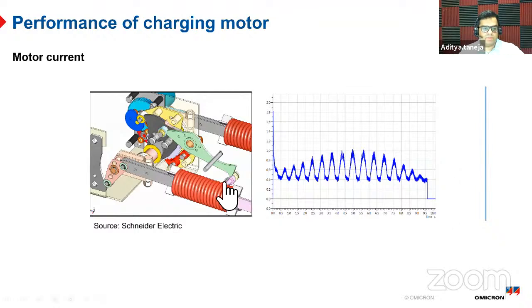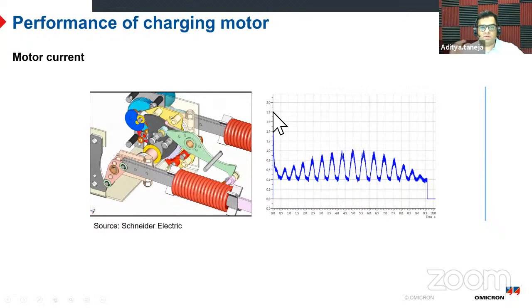Okay, so here you see there was a high inrush current. If the lubrication is less, this current will increase, and there are limits where if it exceeds, you have to replace the mechanism. And then there is a wavy signature which was coming because of the typical design here of the moving part, that lever. So it's very difficult to know what the RMS value is here, but we calculate on a window the RMS value, whatever it may be, and we show it for you to compare, and also the time taken. Again, this test is better done under voltage and over voltage conditions of the motor limits, to make sure this will work in all conditions while it is in operation.